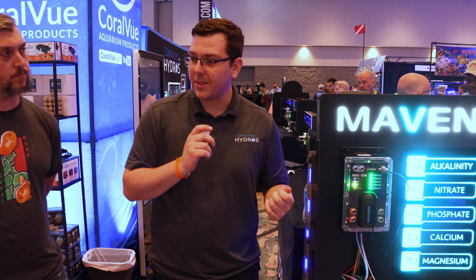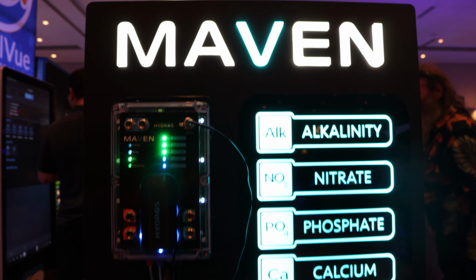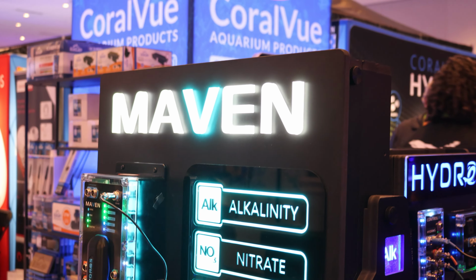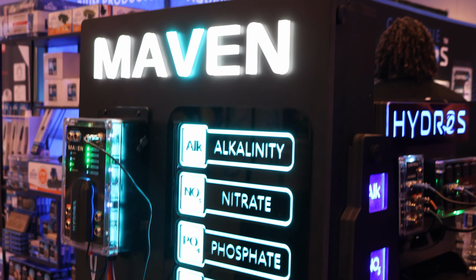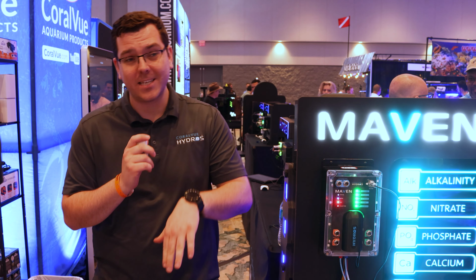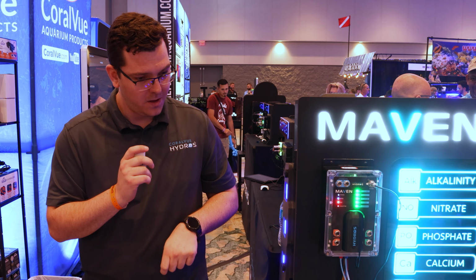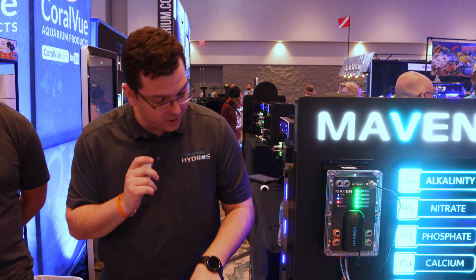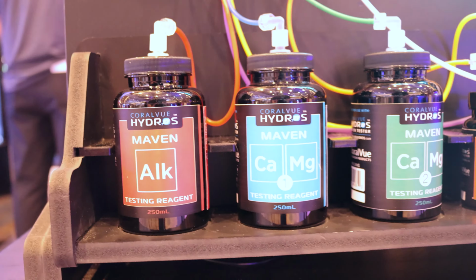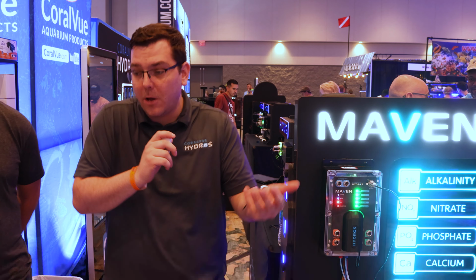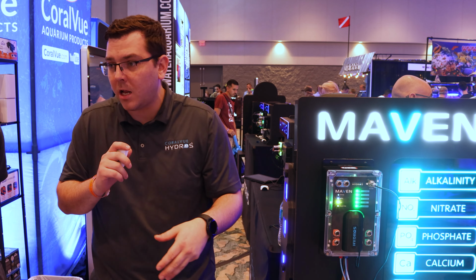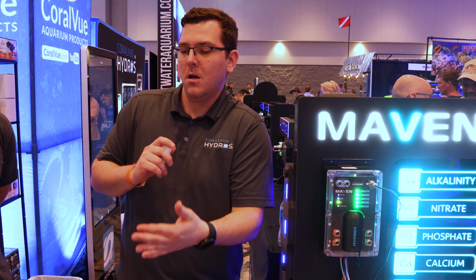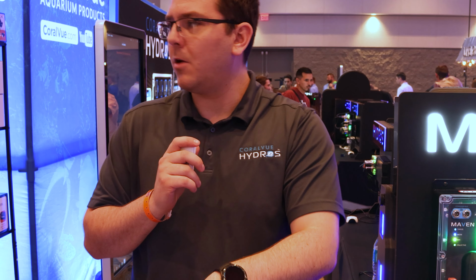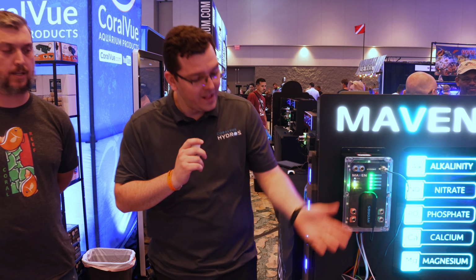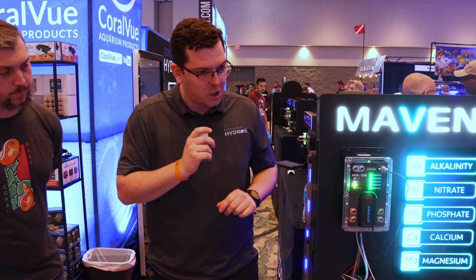And what's really cool about this is after every test that is done, the sample lines are cleaned with RO water and then they're dried using an air pump, which I found very unique. That dries out the sample line on each side, but also that air pump is utilized to agitate the reagents. You don't want them sitting still forever, right? Particles fall down and that can cause problems in the test. We need to agitate those. So let's blow bubbles in there like a milkshake. That's a really fun little nifty feature.